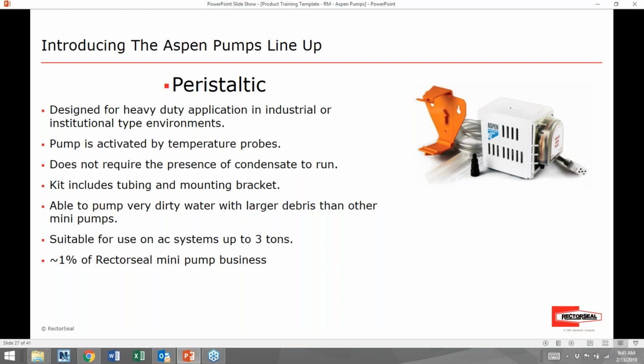The peristaltic pump is designed for very heavy-duty applications, such as industrial or institutional type environments. Whereas all the pumps we spoke about previously require water to flow into a reservoir, which lifts a float, and the float is what activates the pump, this peristaltic pump is activated by temperature probes. Because it is not a piston pump, it does not require the presence of condensate water to run. It can run dry with no damage.